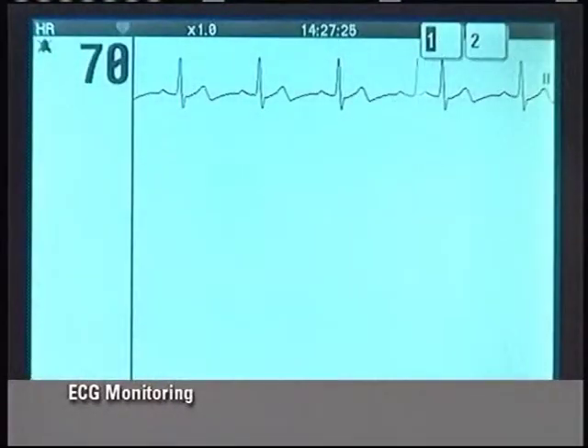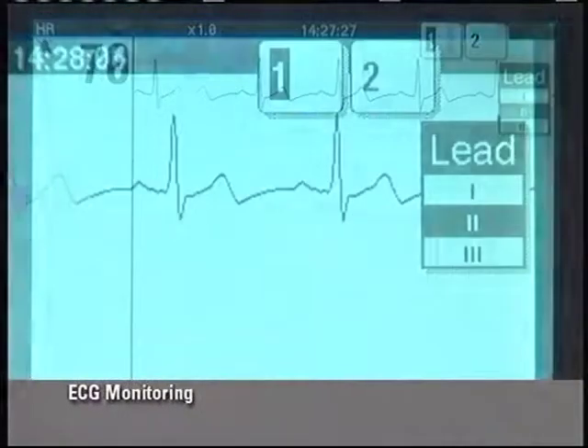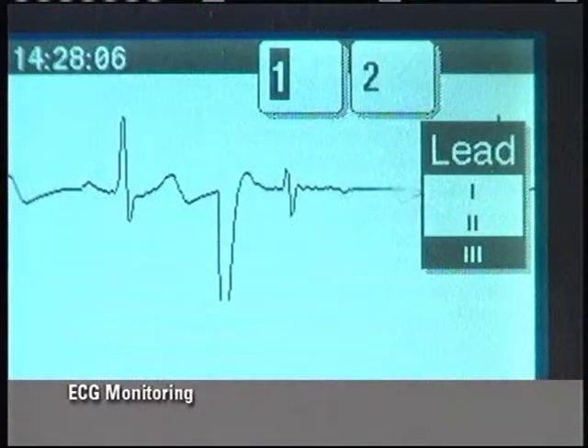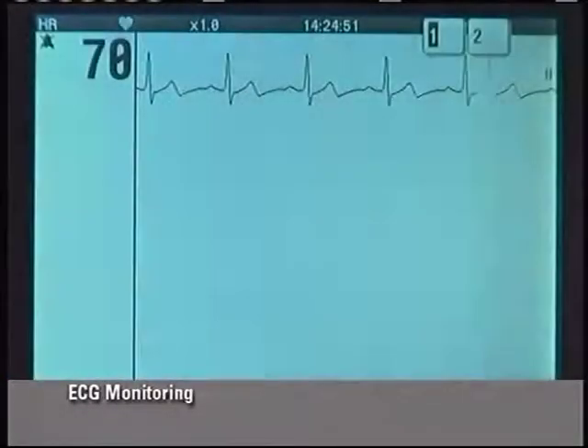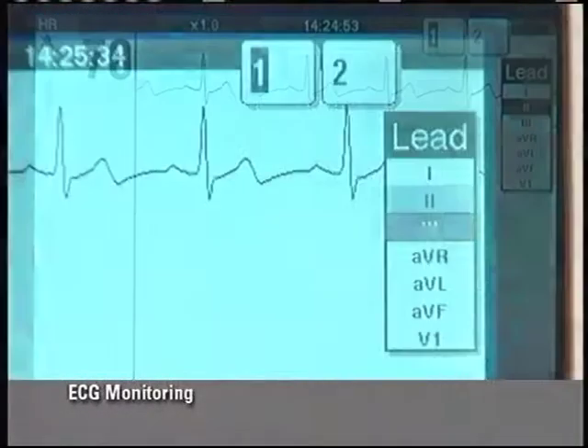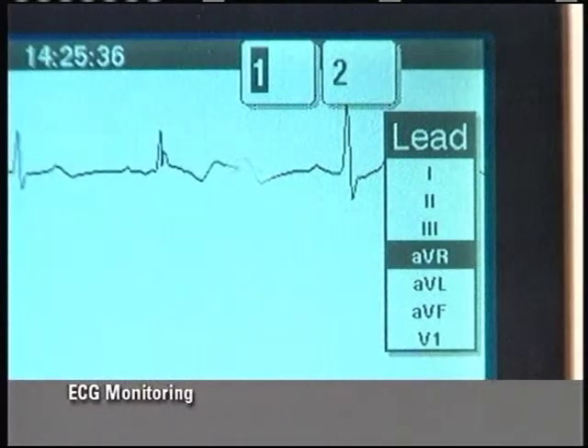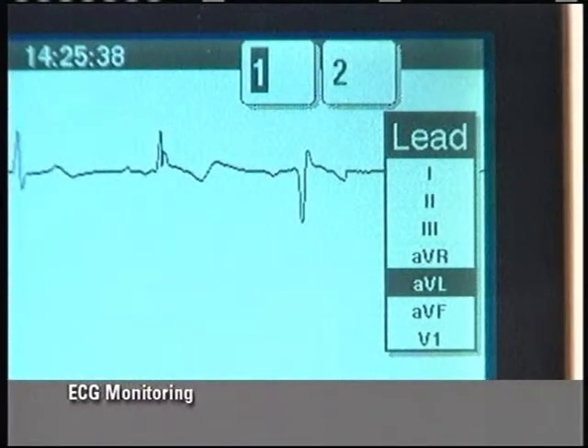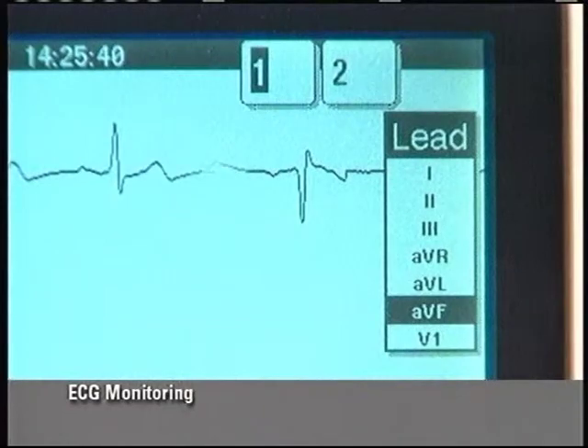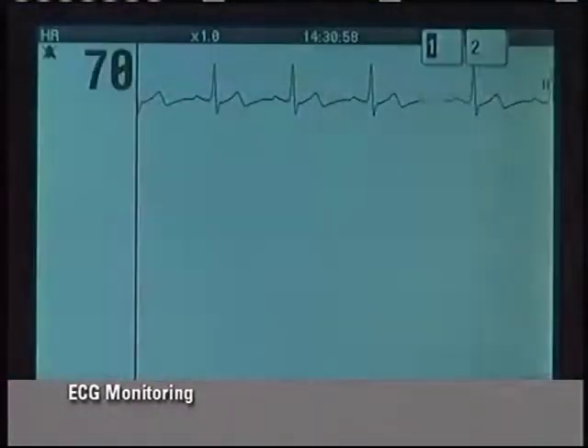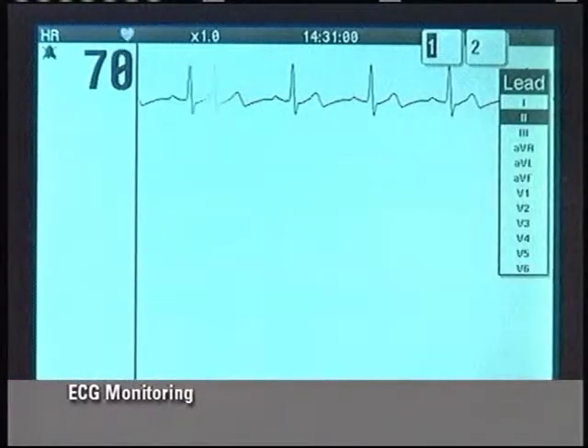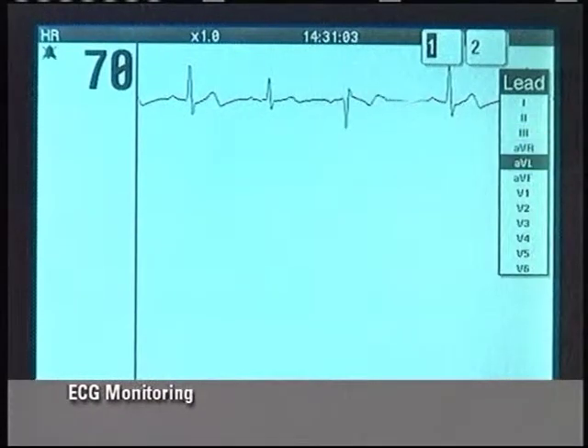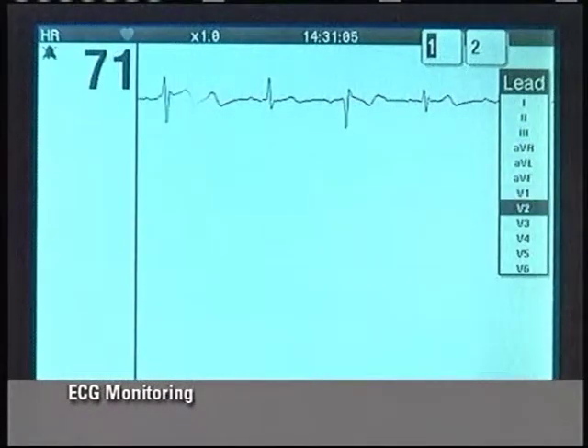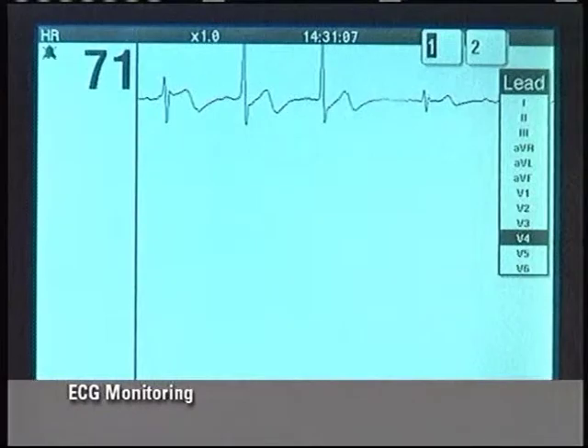When the 3-lead cable is connected, only 3 limb leads, 1, 2, and 3, can be selected for ECG monitoring. When the 5-wire cable is connected, the 6 standard limb leads can be selected for ECG monitoring. In addition, the 5th wire can be placed in any of the chest lead positions. When the 12-lead cable is used, the standard limb and precordial leads are available. Only the 12-lead ECG cable will be demonstrated in this video.